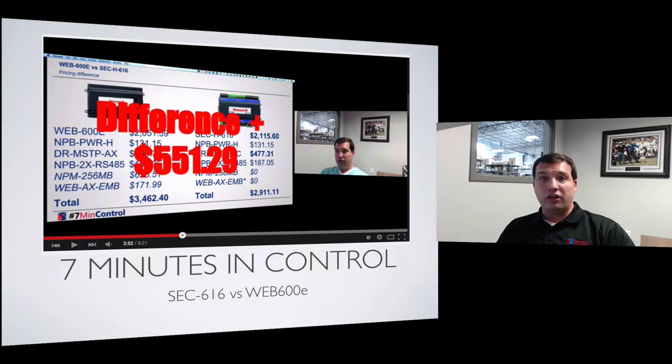Now, one little clarification, you are limited to 60 devices on that security JACE, so if you're going to be over that, you need to look at what you want to do, whether you want to have an extra JACE or whether it just does make sense on this particular application to do a Web 600E. But with this, you're actually going to have a JACE for all intents and purposes exactly like your Web 600, and it's got all those extra things, the embedded workbench, the expanded memory, but you also get those two door readers. So, I'm sorry, not door contacts. You get the two readers in the JACE. All of the door hardware you are going to buy separately.